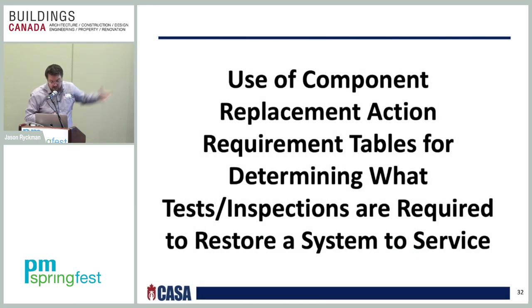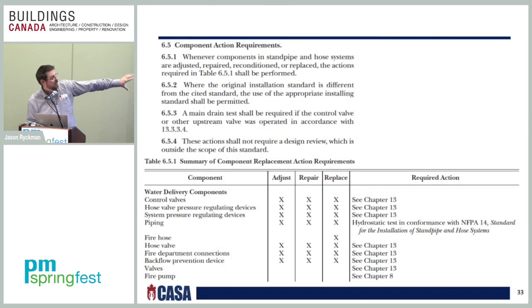Also, another table to be active in understanding is the use of component replacement action tables to determine what tests and inspections are required to restore the system back to service. So you have your system down for some reason. Well, now there's a procedure in place that you have to follow in regards to what actions need to be taken care of. So here's basically what it says in table 6.5.1, summary of component replacement action requirements. It tells you if the component needs to be adjusted, repaired, or replaced, and what is required when your system goes back into service again.